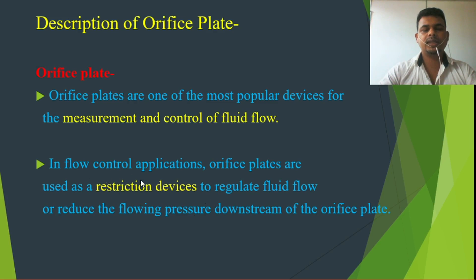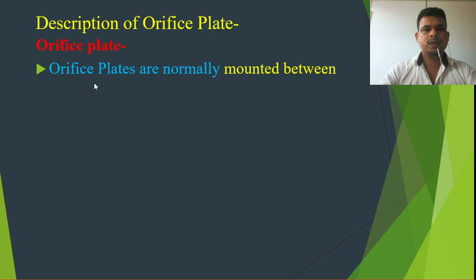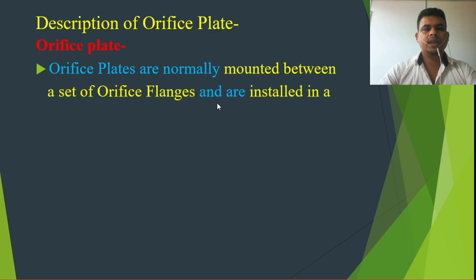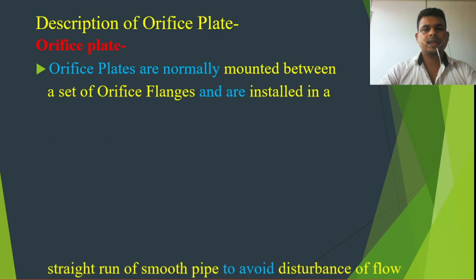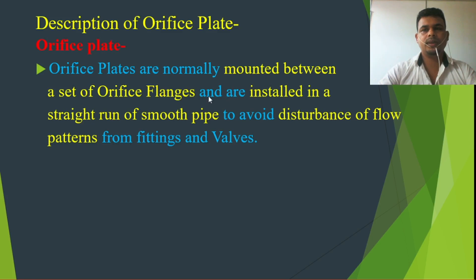Orifice plates are normally mounted between a set of orifice flanges and are installed in a straight run of smooth pipe to avoid disturbance of the flow pattern from fittings and valves. The orifice plate is installed in between the two flanges as I showed earlier, and it must be used on a long straight pipe run.